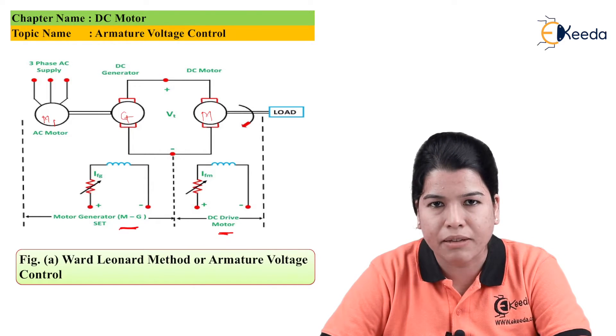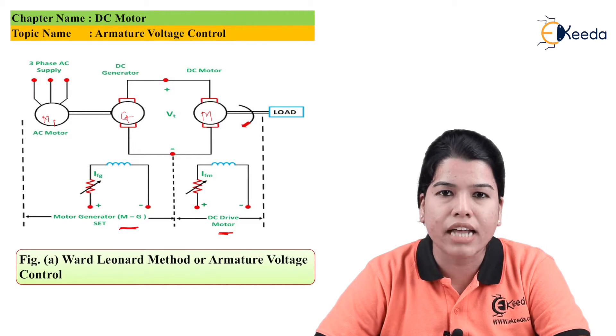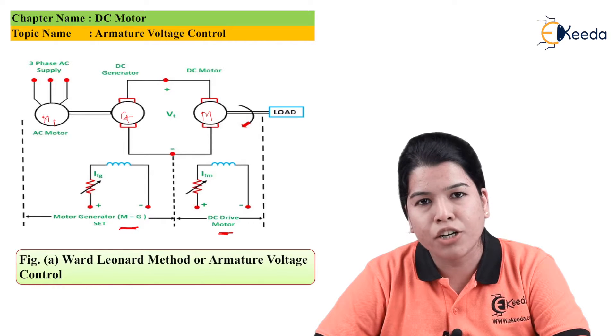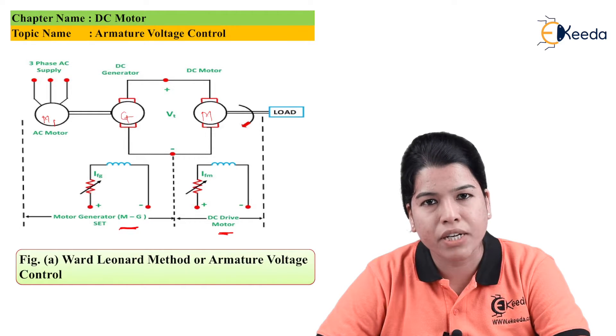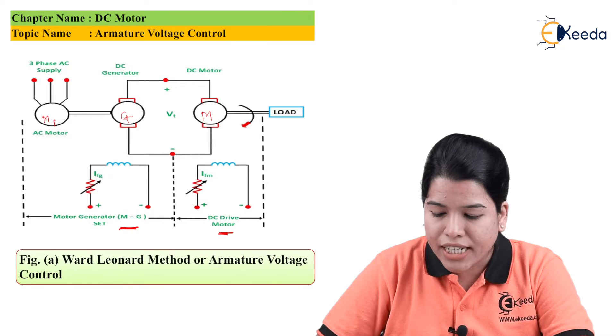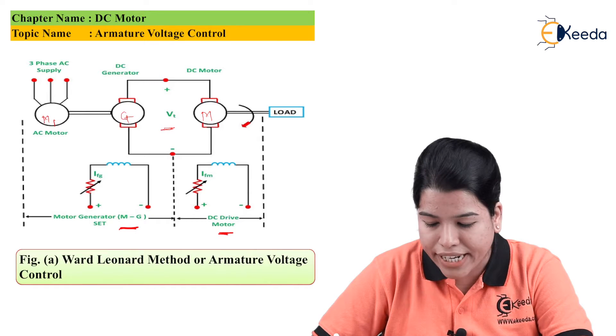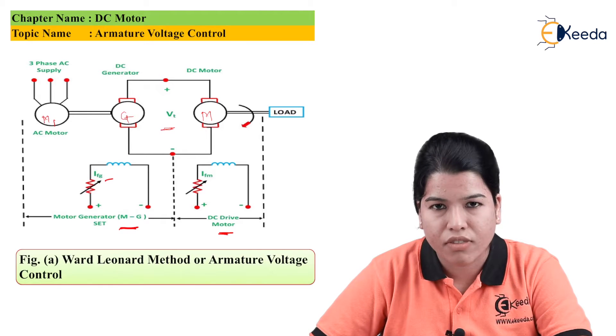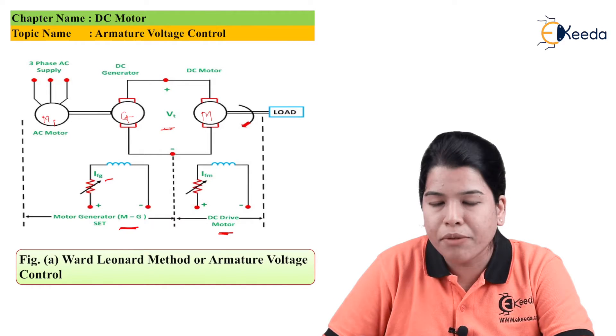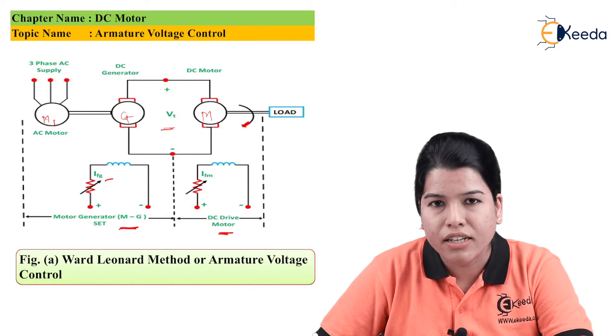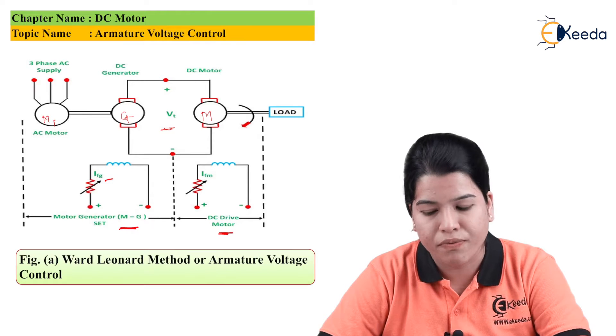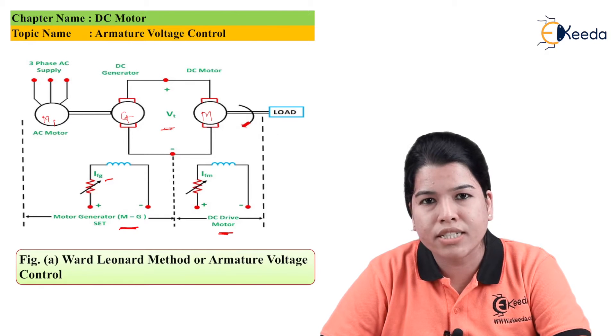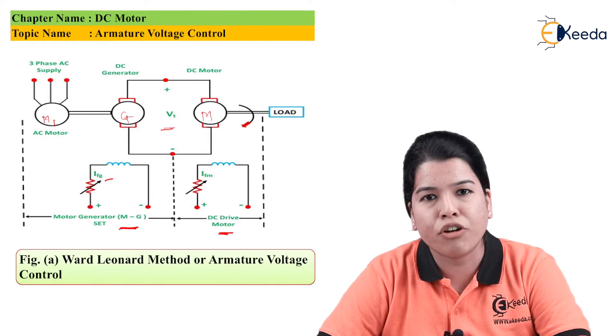In the Ward-Leonard method, armature voltage is controlled. The speed can be controlled below the rated speed as well as above the rated speed. For controlling speed below the rated speed, the generator output voltage Vt can be varied by varying the generator field current IFG. The DC motor's field current, flux, and armature current are all maintained constant at their rated values.